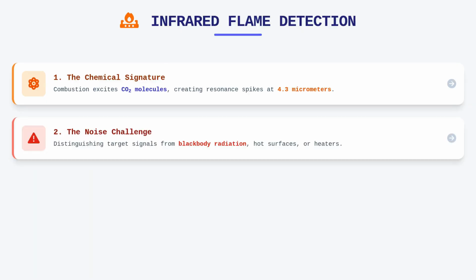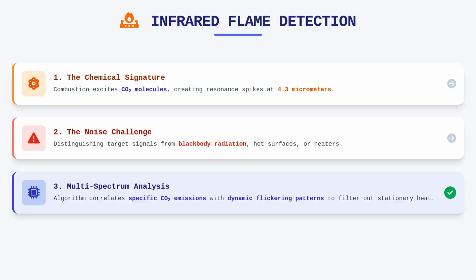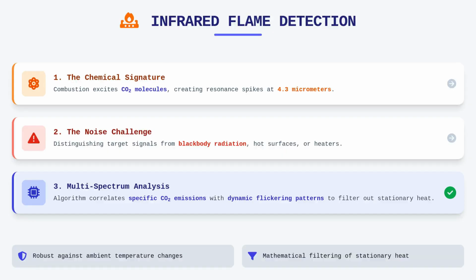However, the challenge arises when we must distinguish this target signal from non-fire sources like hot surfaces, heaters, or general blackbody radiation. To solve this, manufacturers often employ multi-spectrum infrared sensors that analyze multiple wavelength bands simultaneously to correlate the specific CO2 emission with the flickering patterns characteristic of fire. This mathematical comparison allows the processing algorithm to filter out stationary heat sources that lack the dynamic signature of a growing flame.